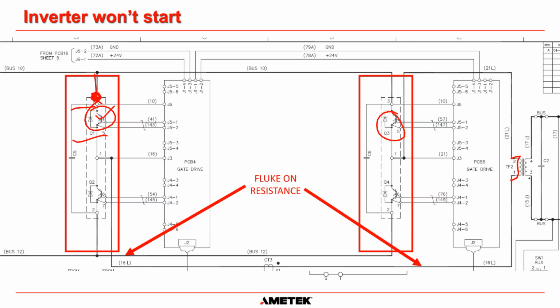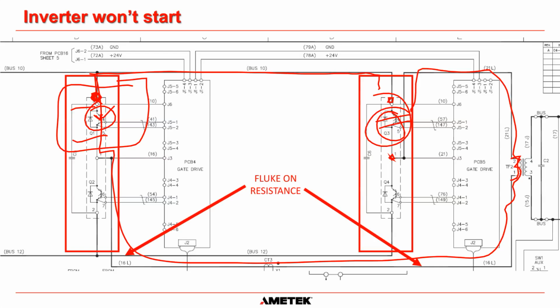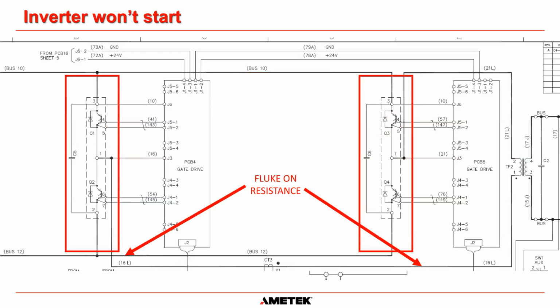So if this has failed and is short circuit, but this one is still good, open, if you went across the collector and the emitter here with this system, with Q1 still in circuit and it being a short circuit, you will read a short, because basically the short will go down here through the transformer and make it look like that one there has shorted as well. So to find out which actual IGBT has failed, you do have to disconnect them from the circuit.